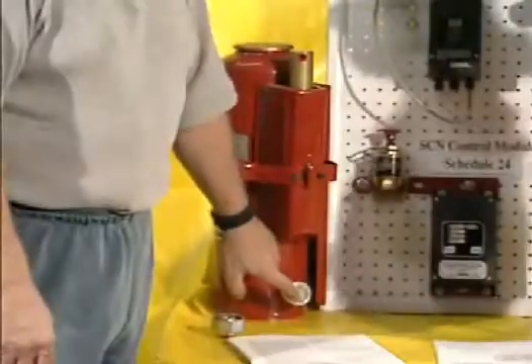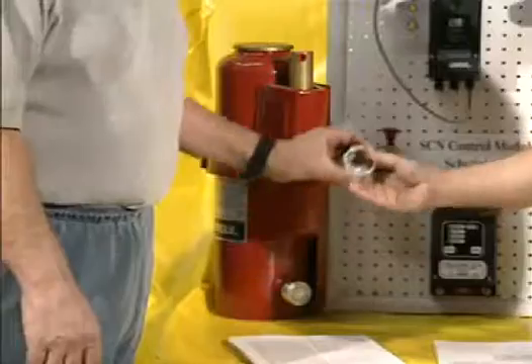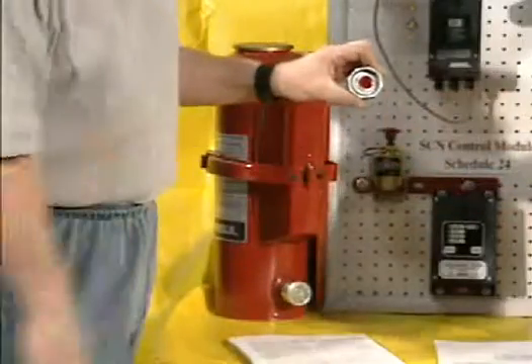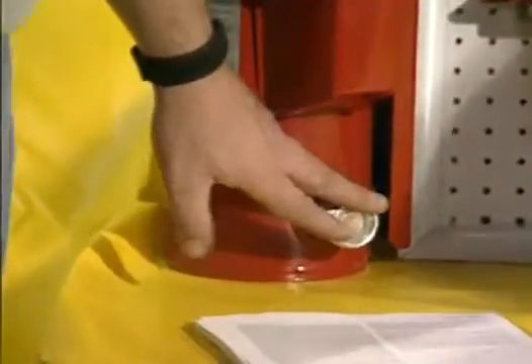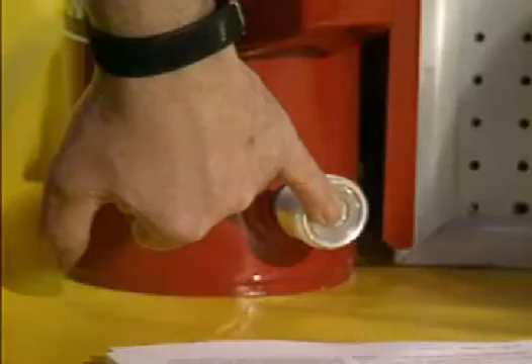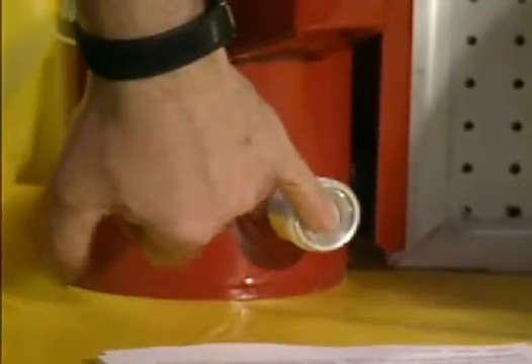Now, isn't there a plastic ring? Right here on the outside there's a plastic ring. So it needs to be against this fitting? Against this shoulder right here. It prevents it from falling out. Okay. These need to be changed on a semi-annual basis. These bursting disc unions need to be pulled out. They need to make sure that that orifice is clean.